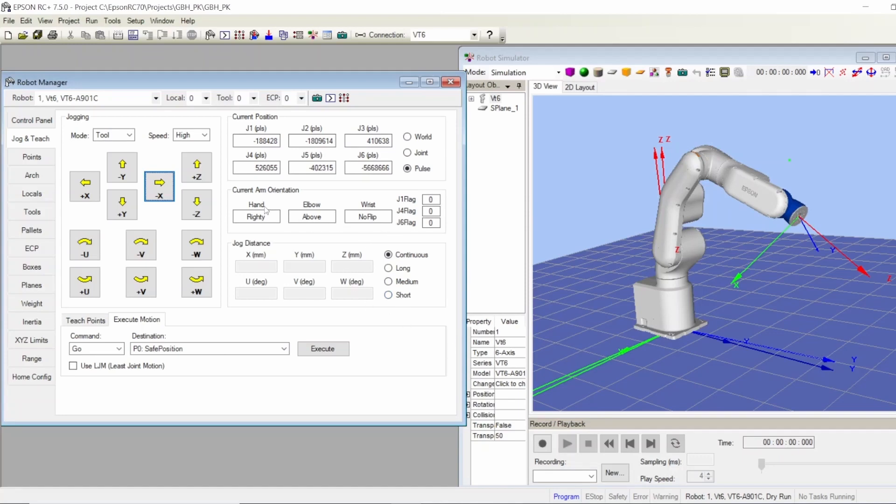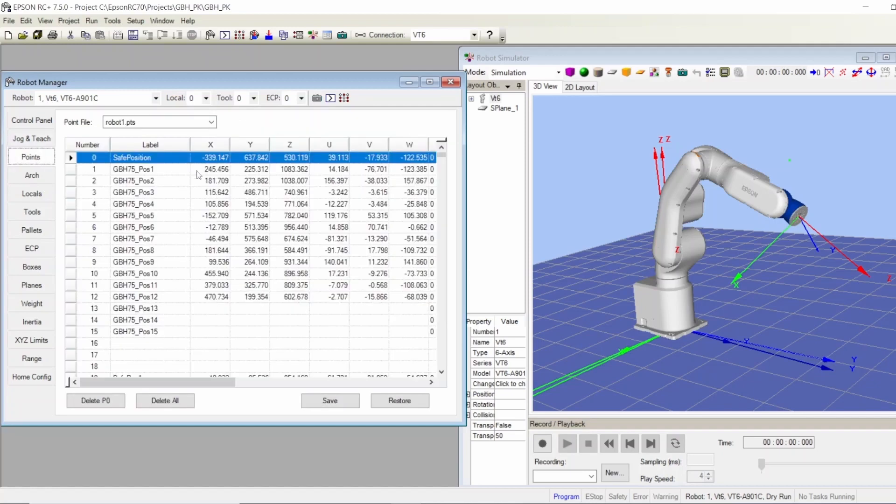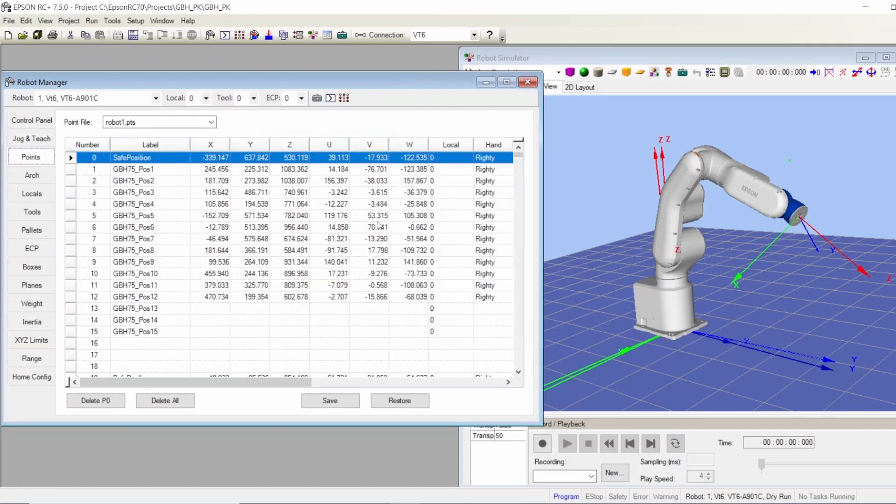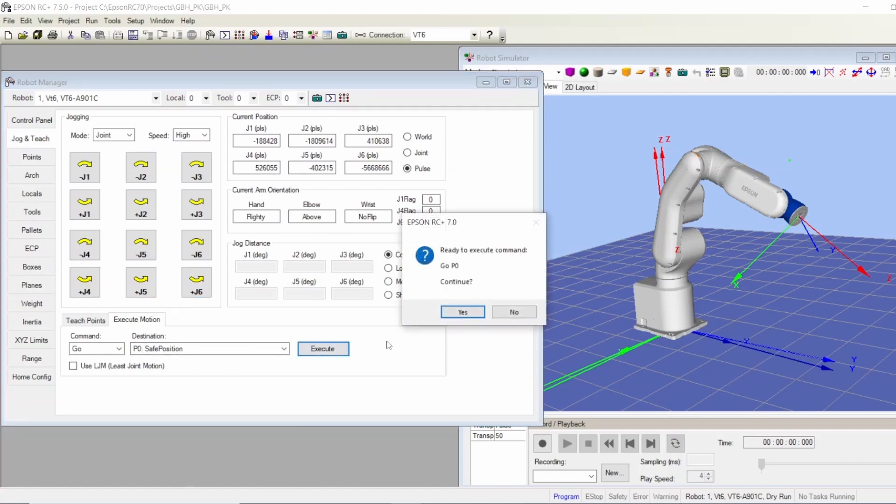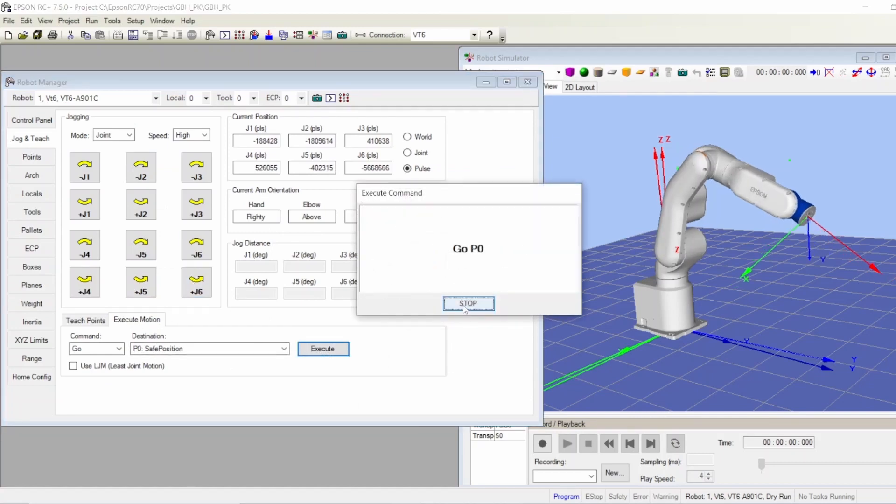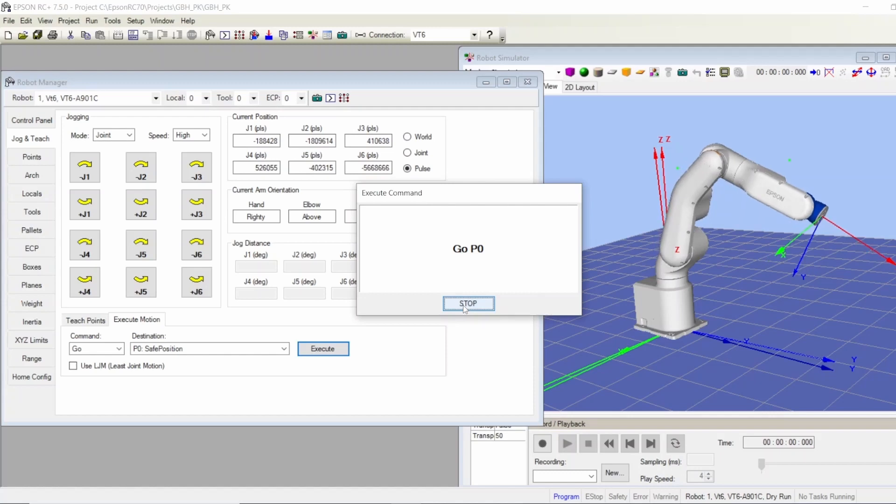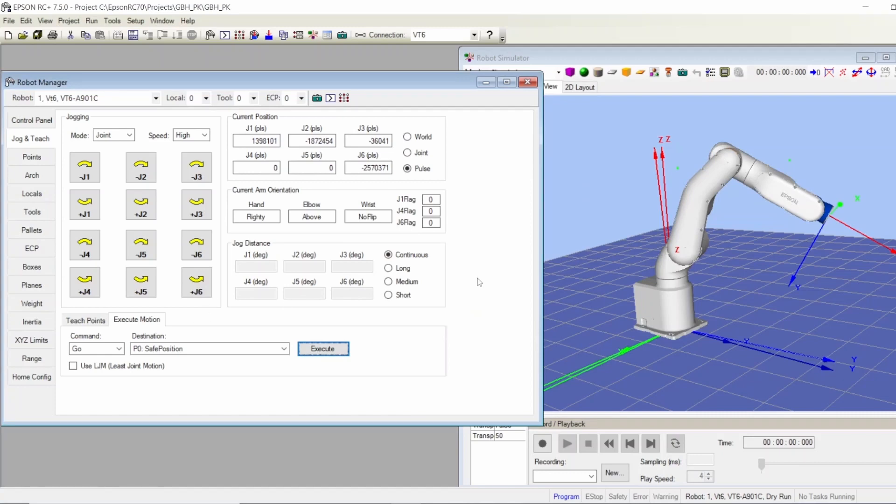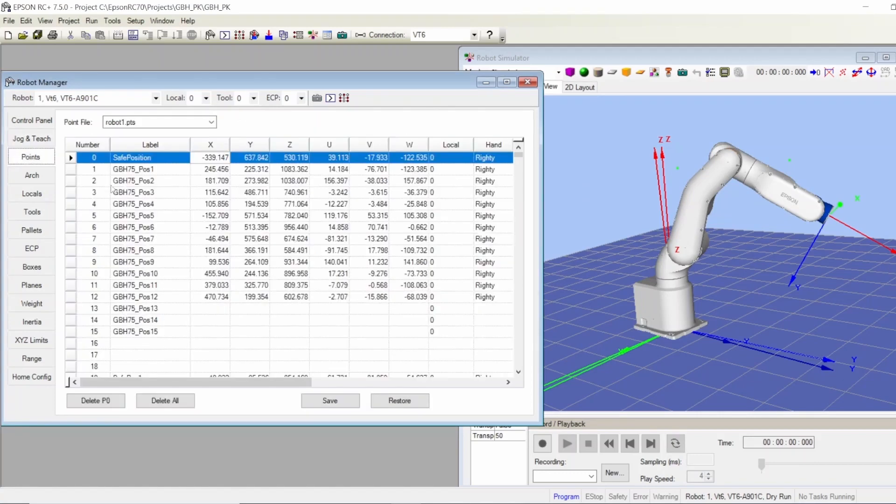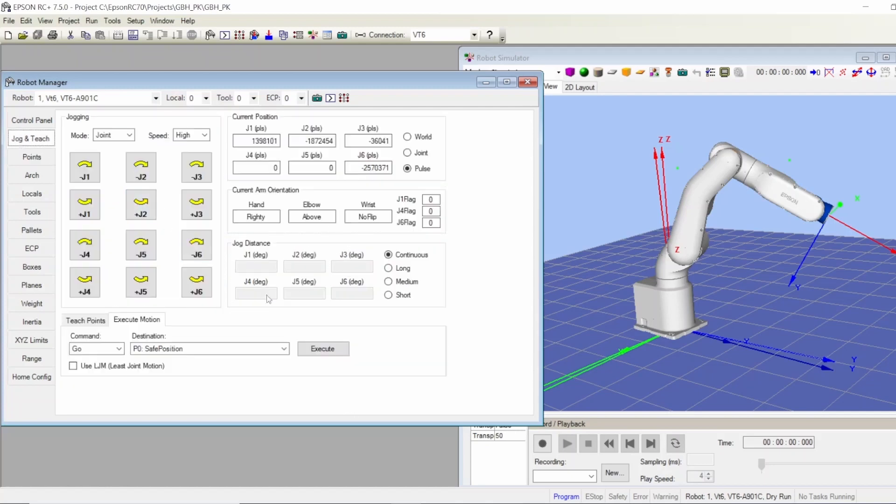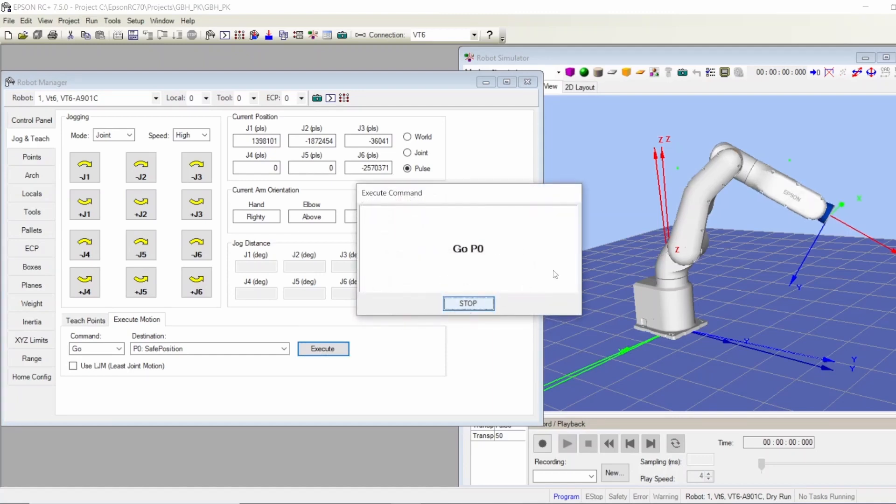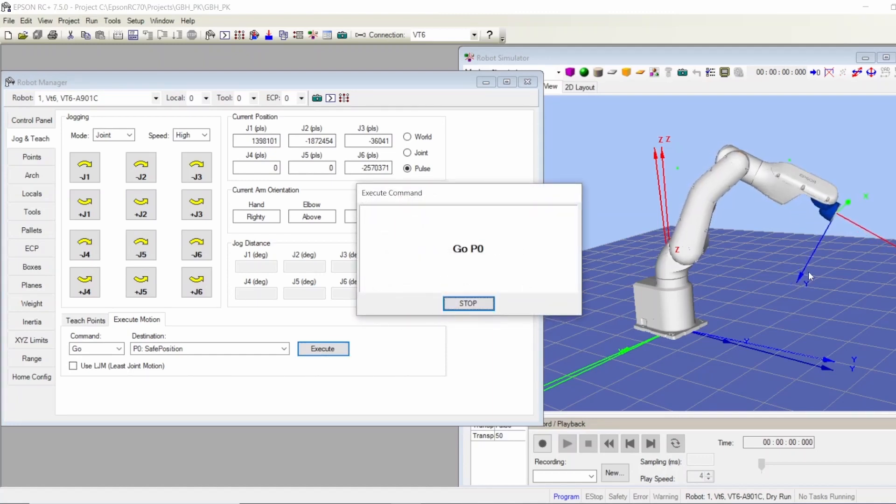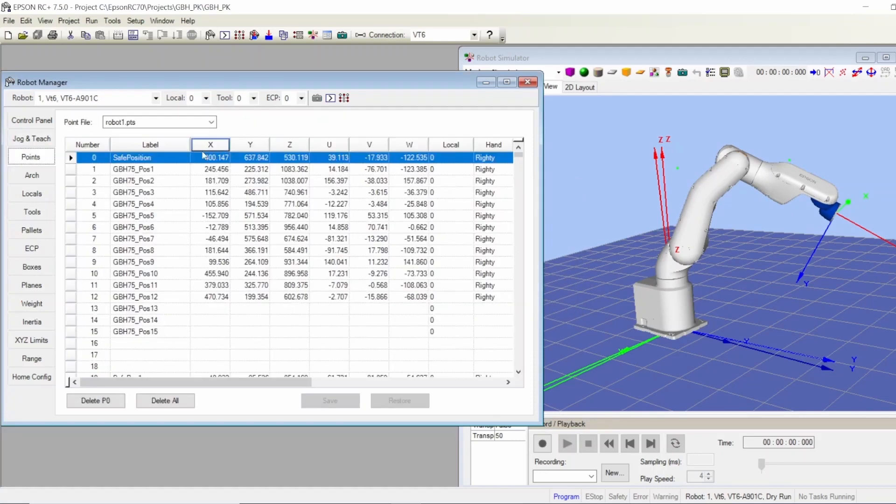That's how you do it. When you finish, you have all these points here. If you want to type to change the position for safe position, for example, X is 339. Let's go there first, let's go to our safe position, execute. Now it's in our safe position. We can come to the point in the safe position X and change it to minus 400, save. Now if we tell it to go to the safe position, it's going to move to minus 400. There we go, it moved.